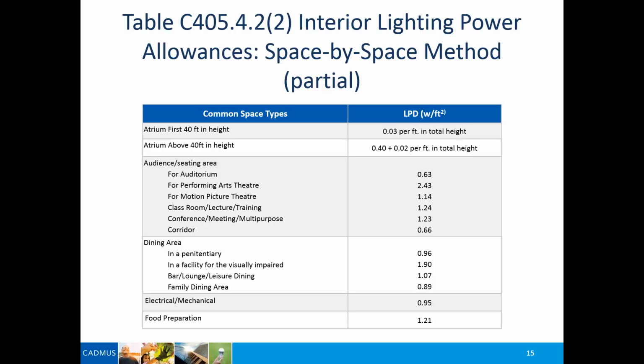So you can still maintain foot candles very easily, even with lower lighting power densities, because the technology we're using right now is so much more efficient than the technology we used before. And the Illuminating Engineering Society in North America, these are actually numbers that came from the ASHRAE standard. ASHRAE uses the identical lighting power density numbers, and these go through the ASHRAE lighting committee. IESNA is represented on that committee, and they've said, yes, we can do this.